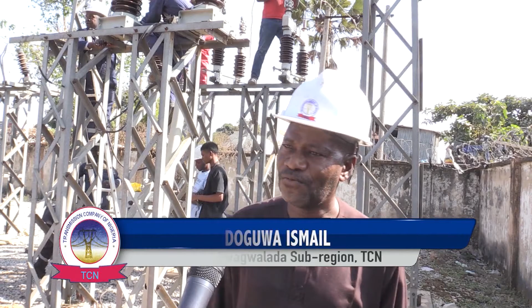The capacity of this station, we have about 5 transformers here. We have T1 at 7.5, and T2 we have 45 MVA. Then T3 we have 30 MVA, T4 we have 60 MVA, and T5 we have 60 MVA. So in essence, we even have T4 that is free, so we have enough capacity for radiating more feeders.